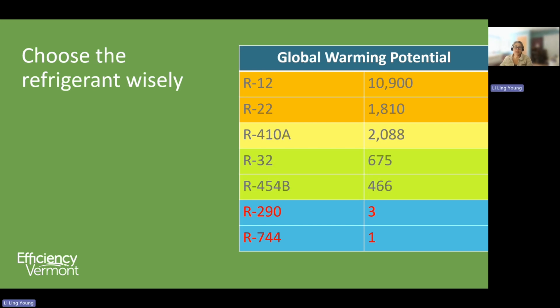Some refrigerants are much less damaging, and some refrigerants are so low in their global warming potential that they don't even get recovered. Right now, pretty much all you can choose from is R32 and R454B. But soon, codes will catch up with the natural refrigerants, and we'll start to see HVAC with super low global warming potential. Even now, I can think of a couple of heat pumps that use R744. When you have a chance to choose a more benign refrigerant, do it. It's one more thing you can do to minimize the impact of refrigerant leaks. Your customers might even appreciate the option.